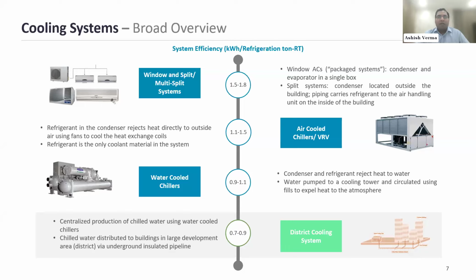Then we have slightly bigger equipment. We have VRV, which is variable refrigerant volume, which is again a DX system. A DX system means refrigerant is used directly for the cooling. There is no secondary medium. Then we have the air-cooled chillers. Air-cooled chillers utilize a secondary medium, mostly water.